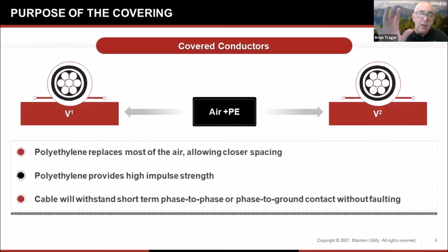So what we do is put a little bit of polyethylene on the phase conductors, and the poly, which is a much better insulator, replaces most of the air, so we can bring those phase conductors closer together and still have a very high BIL, a high 60 hertz withstand, and that cable will withstand short-term phase-to-phase contact, phase-to-ground contact, phase-to-tree contact without suffering a fault.